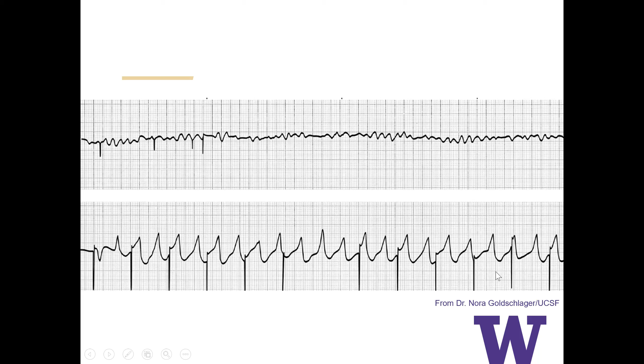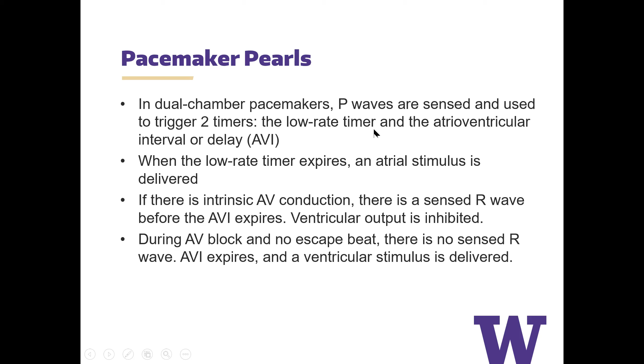So pacemaker pearls, I'm just going to leave you with a couple of slides on the pearls of pacemakers. In dual chamber pacemakers, P waves are sensed and used to trigger two timers, the low rate timer and then the atrioventricular interval or the atrioventricular delay. So two timers in dual chamber pacemakers. When the low rate timer expires, an atrial stimulus is delivered. If there is intrinsic AV conduction, there is a sensed R wave before this atrioventricular interval expires, and the ventricular output is inhibited. During AV block, and you have no escape beat, there is no sensed R wave, this atrioventricular interval expires, and then the ventricular stimulus is delivered. So that means it's actually paced.